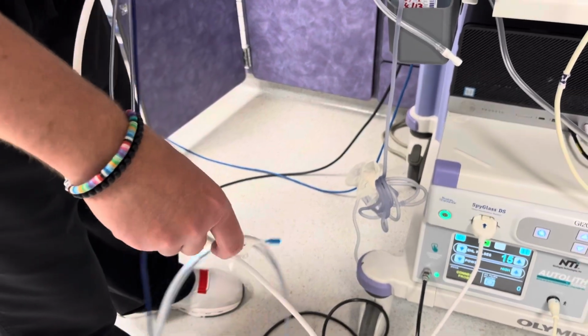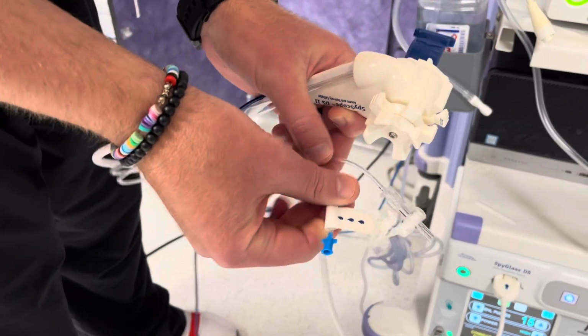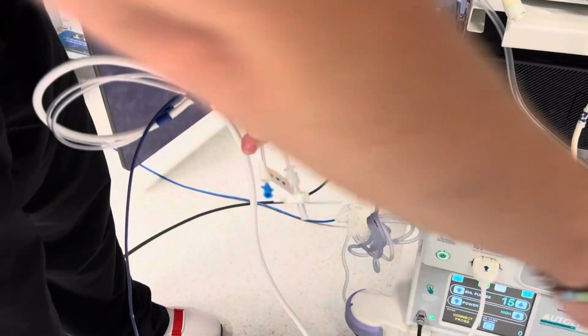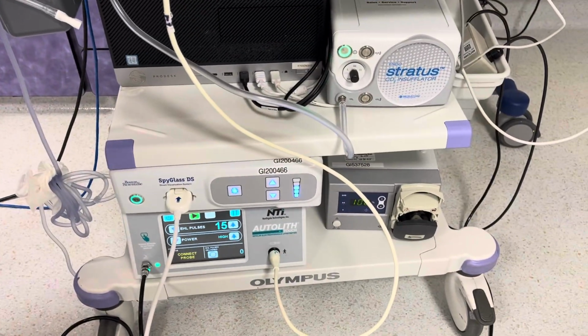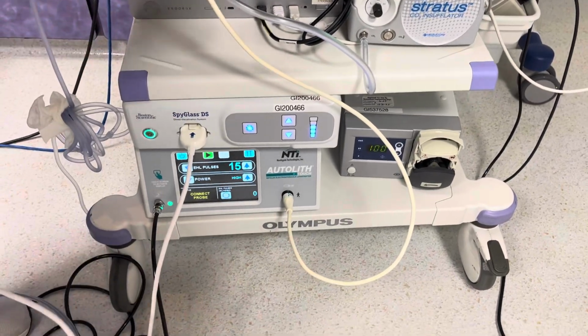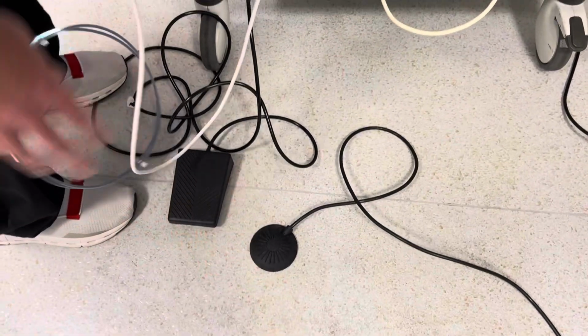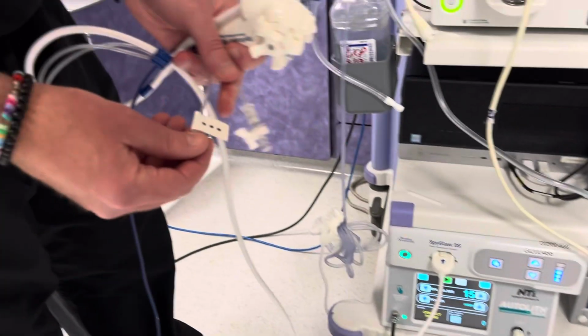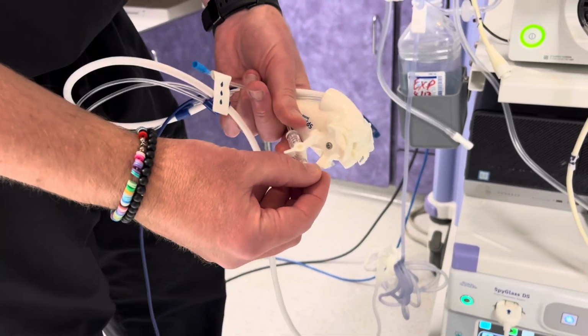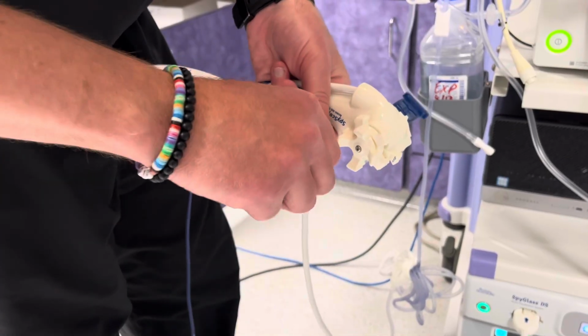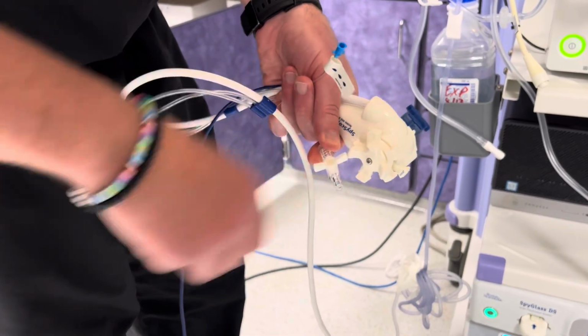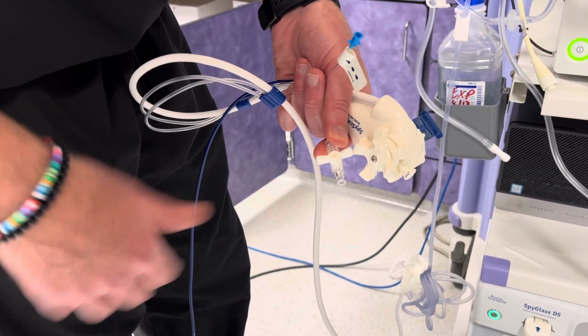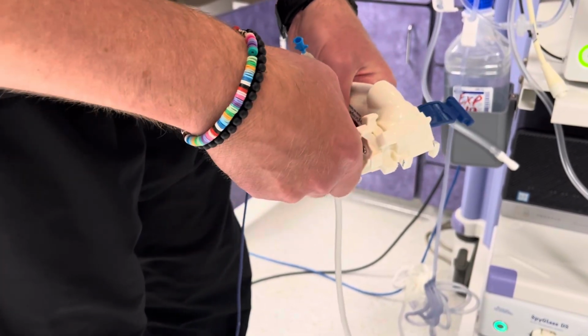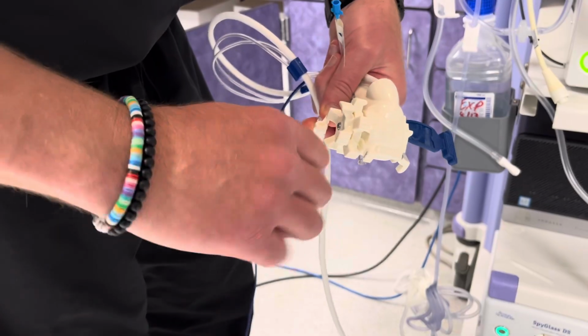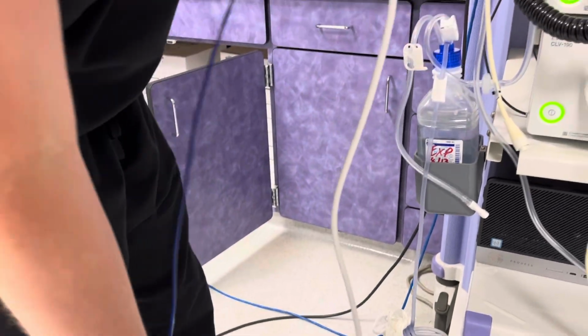There's two ports on the side of the Spyglass catheter. One has water droplets. This is where you will connect your irrigation pump tubing directly to here. And then your irrigation foot pedal that you use for colonoscopy will control irrigation through Spyglass. The second port is for suction, but not traditional suction. So likely the best thing to do with this port is to turn the stopcock into the closed position. Unless the physician wants to aspirate through Spyglass, they can open it. You can attach a 20 or 30 cc syringe and you can suction out aspirate from the bile duct.